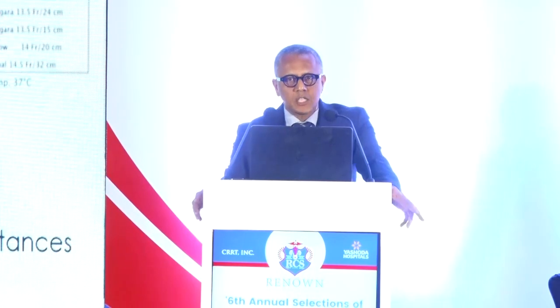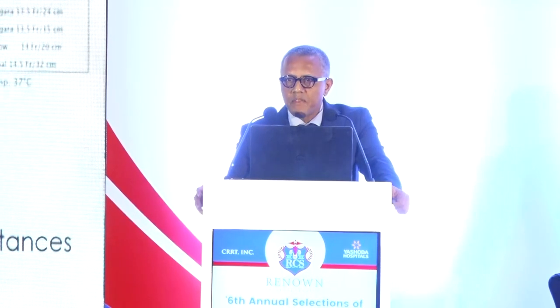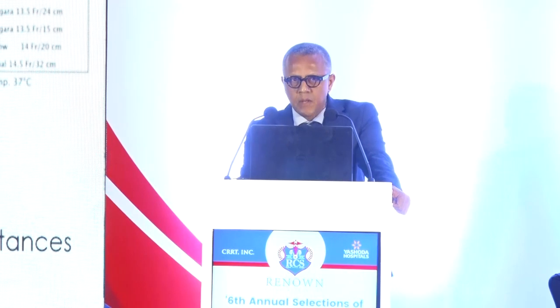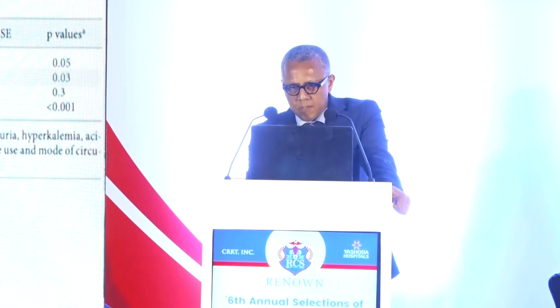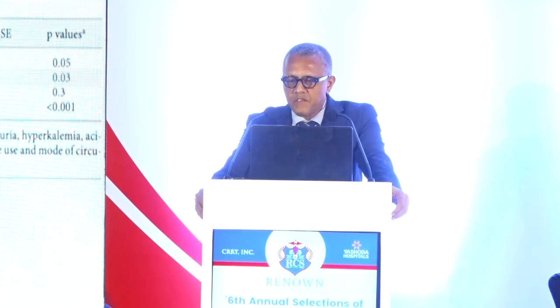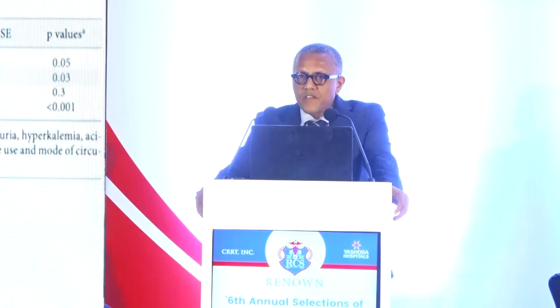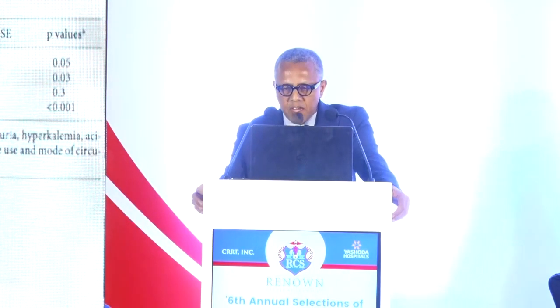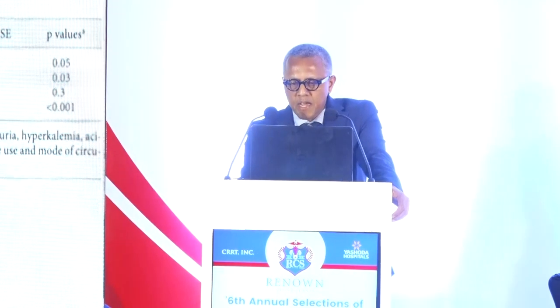This has been experimentally shown: for any given blood flow, larger gauge catheters greater than 13 French had significantly lower resistances compared to smaller gauge catheters of 13 French or less. In practice, most would use catheters in the range of 11 to 14 French, with 12 to 13 French likely being the sweet spot for CKRT. The role of catheter size was highlighted in the RENAL study, where femoral access was associated with a 1% decrease in CKRT dose delivered, but use of a 13.5 French catheter was associated with a 4.2% higher dose delivery.